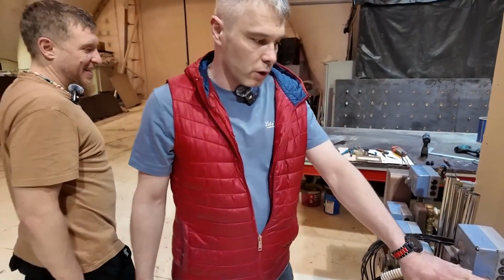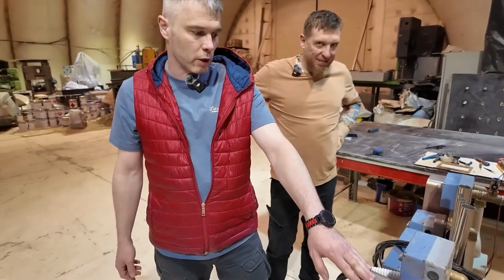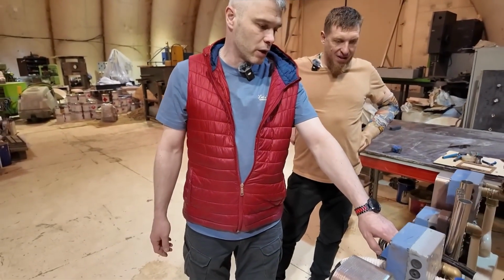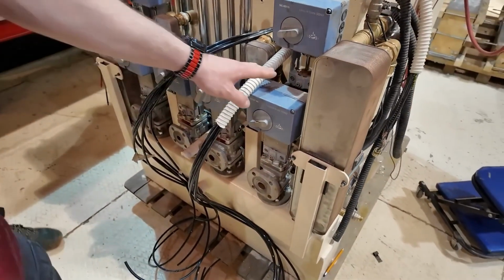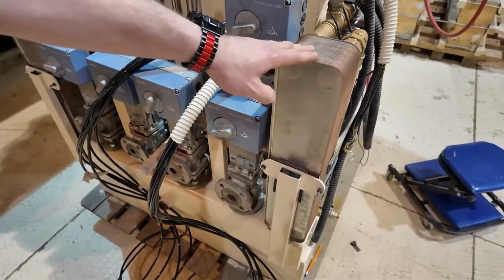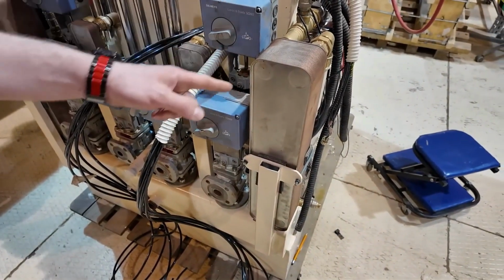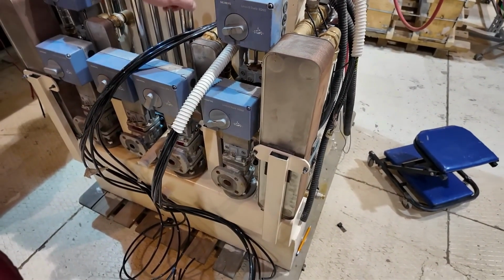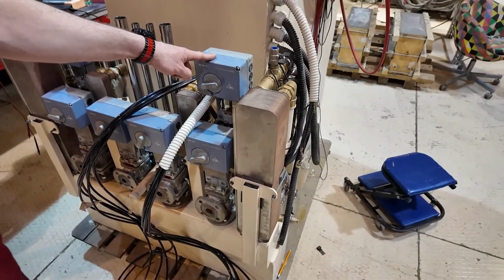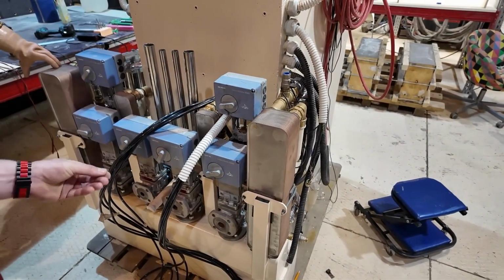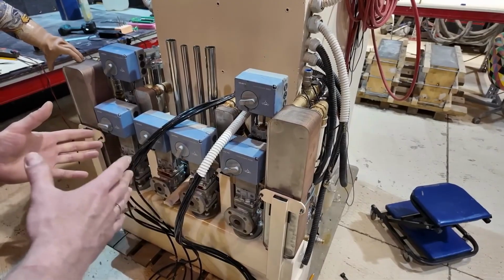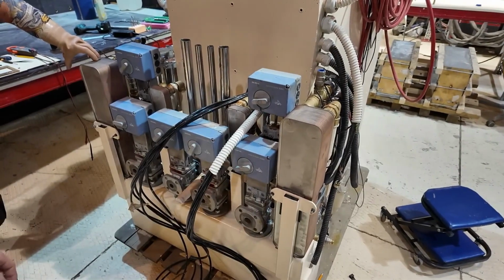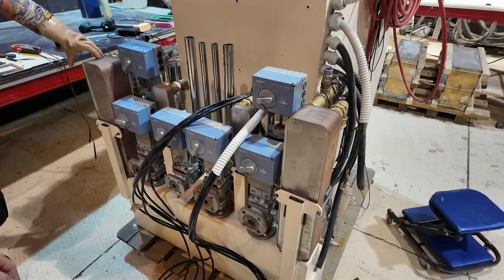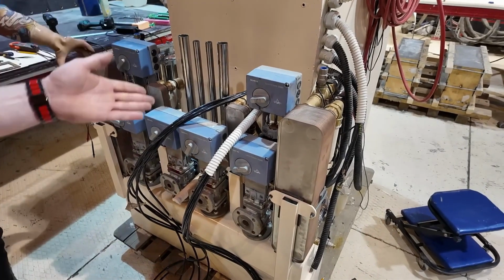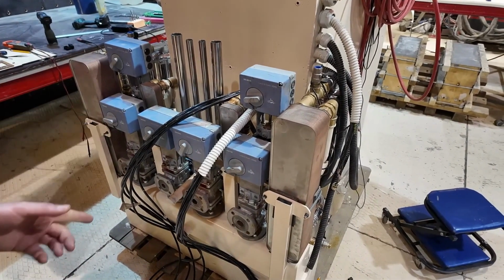For temperature measurement, each of our motors has a main heat exchanger, which is the motor's heat exchanger, and a slightly smaller heat exchanger for the test stand's controller. And there are 6 servo valves installed. This one controls this heat exchanger and the temperature that will be supplied to the motor and the controller. And this servo valve controls the flow of liquid through the controller. For example, if we have a task where a small pump will be installed on the equipment, we need to see how much the motor will heat up, or the controller.